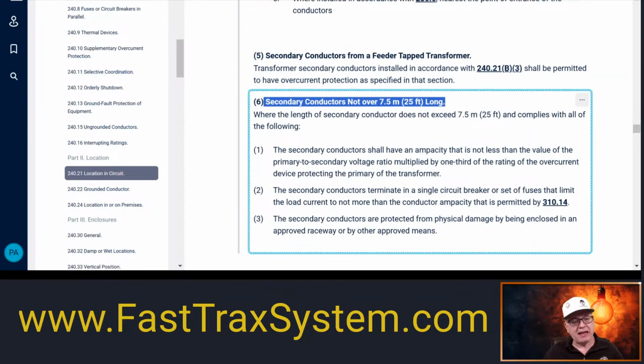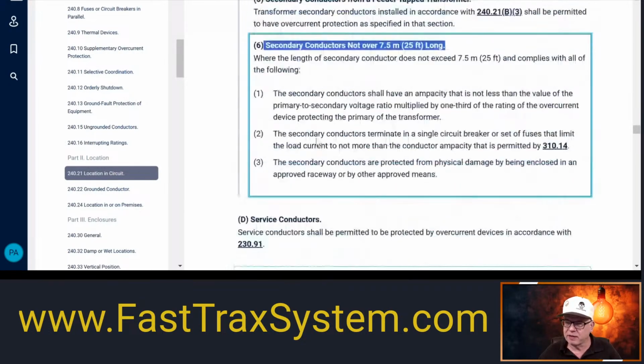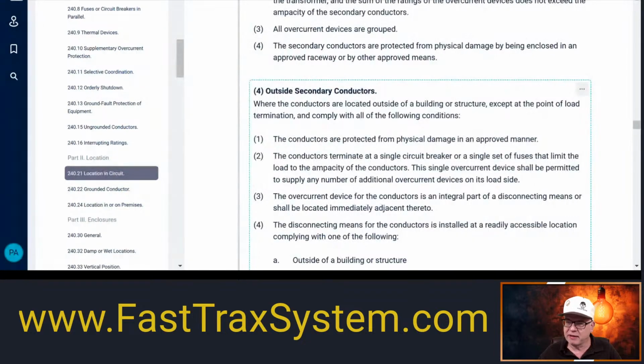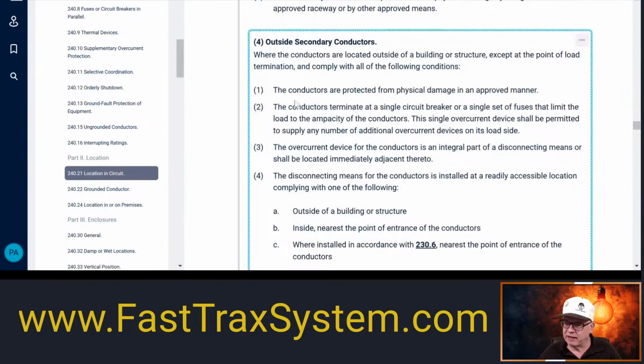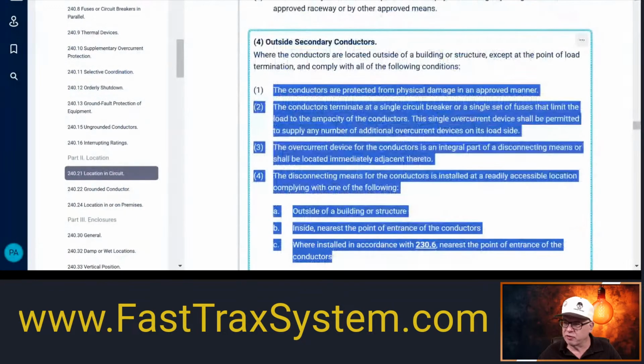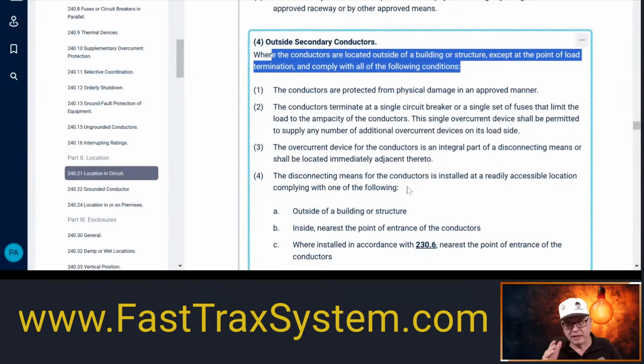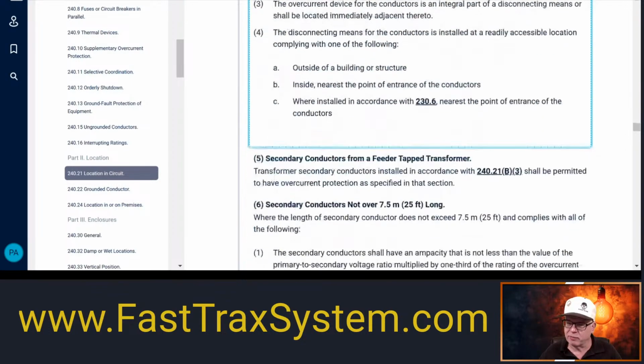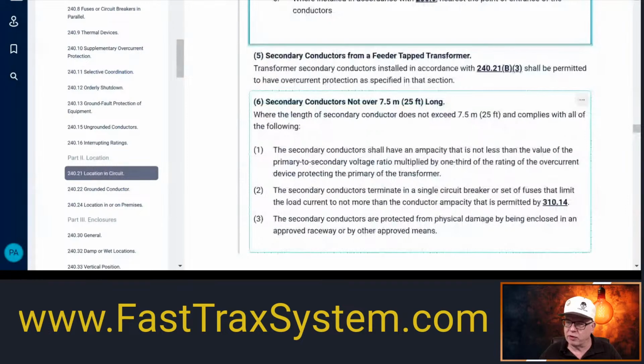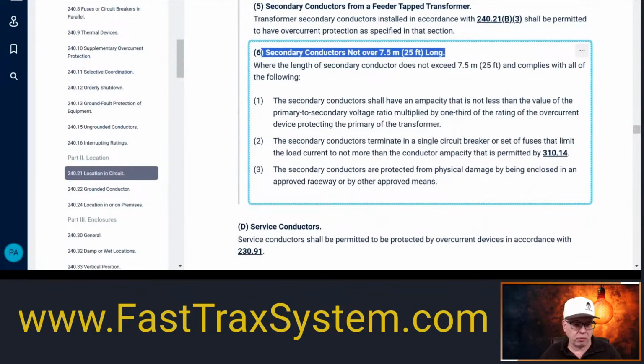Somebody did ask a question about when these secondary conductors can be unlimited in length. We will be talking about that, but there are outside secondary conductors, and they still have conditions to meet. But you'll notice there's really no length limitation on those. That's because those conductors are outside, not inside, not acting like something that, if it were to burn up, could cause a problem with the building. These are outside of the building, so these are not an issue. But we're not talking about those today. We're going to focus on this rule right now. At least get this one out of the way, and then we'll see where it goes.